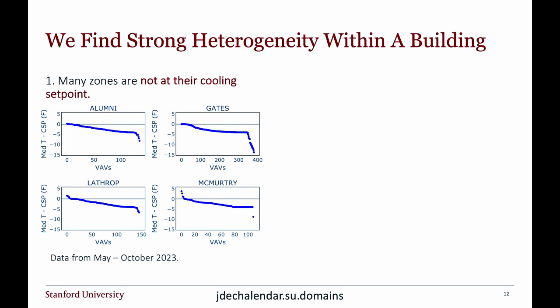So here, these pictures for four of the buildings I showed earlier are showing the difference, the median of the difference, between the temperature in the zone and the cooling set point. So the temperature the zone is actually at versus the maximum temperature it's allowed to be at. Something that's negative here means the zone is cooler than it wants to be or than it's allowed to be.